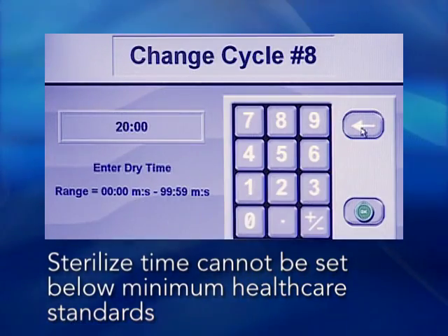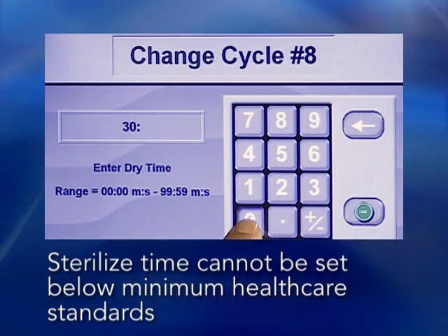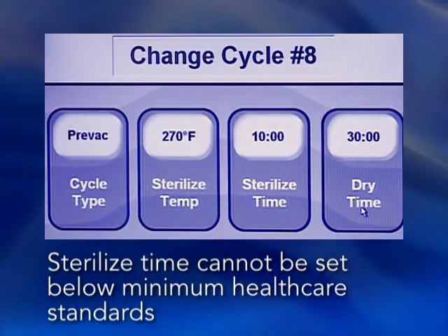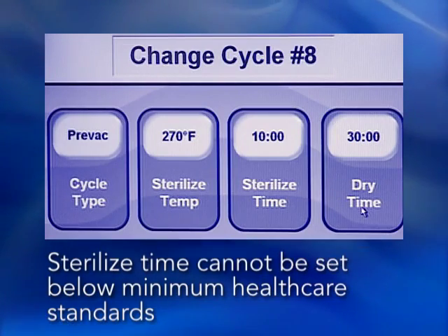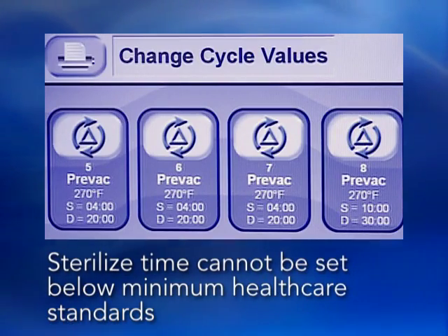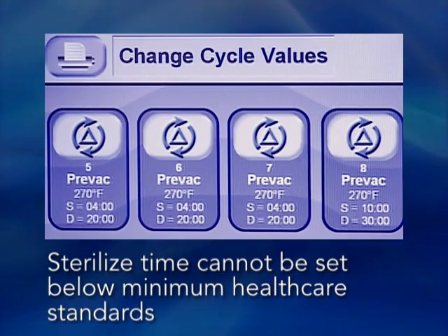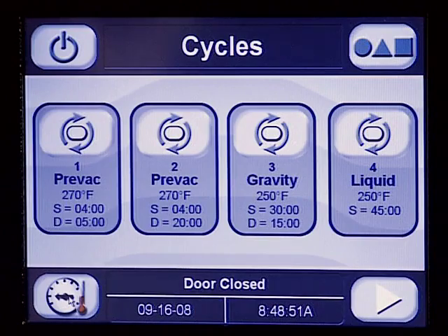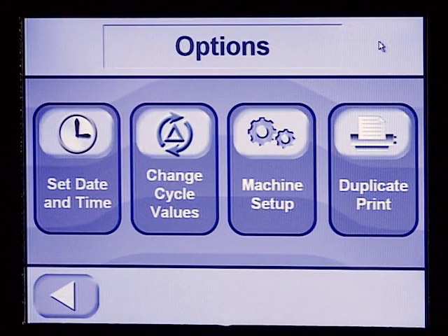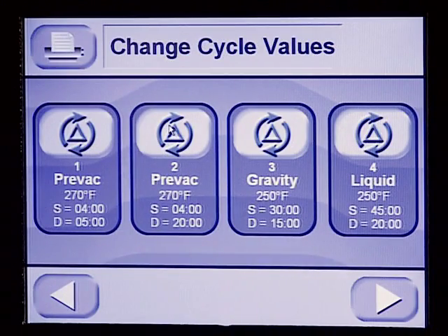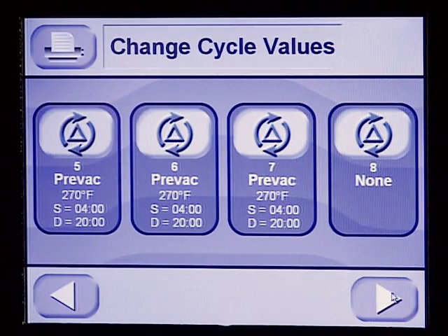If cycle parameters, sterilize time, dry time, or temperature, other than the factory set values are required, it is the responsibility of the healthcare facility to consult and follow the device manufacturer's written instructions for processing. To adjust the sterilizer's operation, press the Options button. The Set Time and Date, Change Cycle Values, Machine Setup, and Duplicate Print buttons are displayed. To change cycle values, press the Change Cycle Values button. Then press the cycle button number that you want to change.